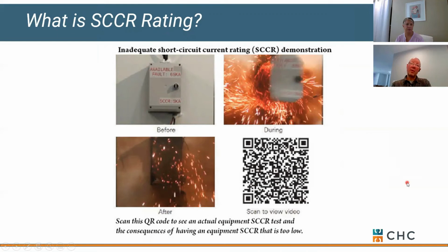I know we won't have a lot of time to talk about this, but SCCR, or short circuit current rating, on a panel is something we're seeing electrical inspectors pay a lot of attention to. Basically, how much current you can get if a transformer fails within your building. We want to make sure that every control panel is being supplied with an adequate SCCR rating. A lot of this ties back into the electrical specification for a project, making sure the panel has components that can handle a high inrush. Just be careful if we're dealing with new construction. You might want to make sure we have an SCCR rating addressed. Our standard is 5K, or 5,000 amps, but you can get them as high as 65 or 100, depending on how much inrush you could potentially see.